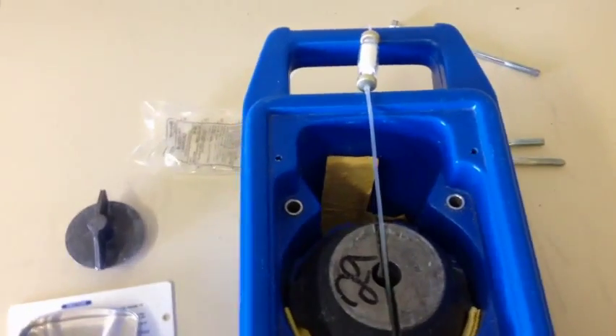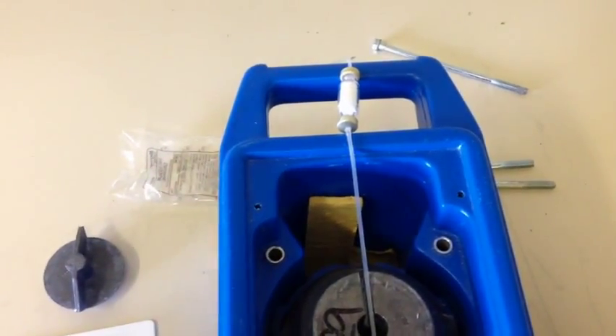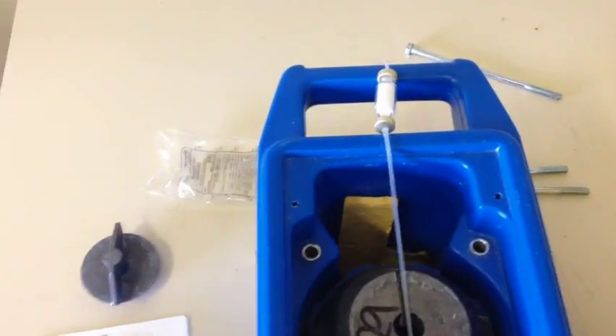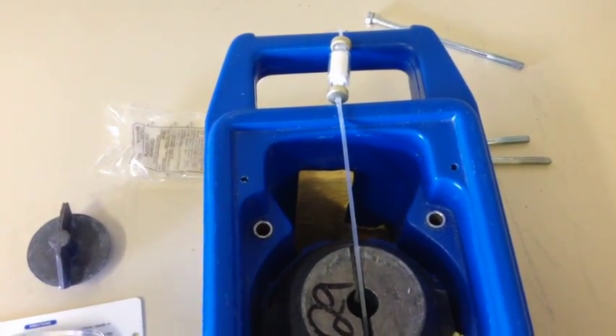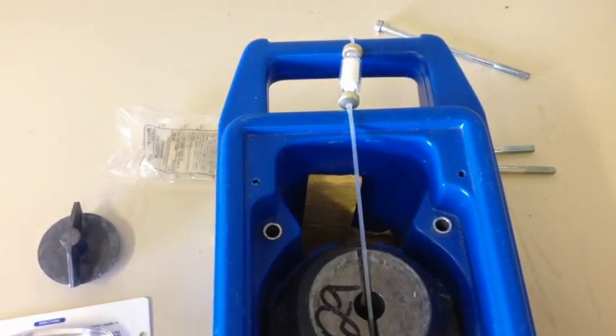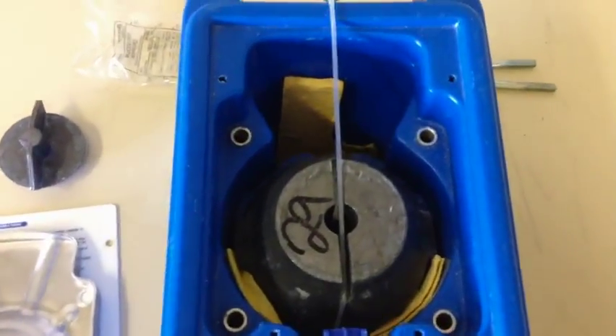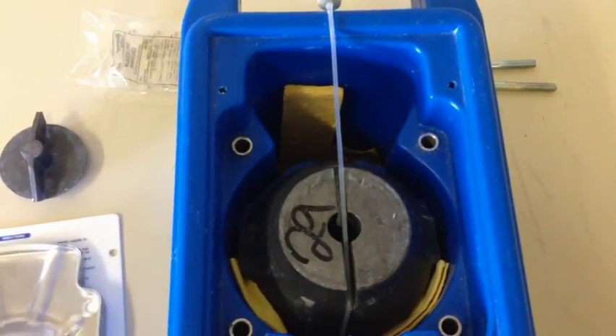You could top it up through the port, but in most clinical environments 250 mils is not going to be eluted in a week. It might become an issue if you're using a generator over a two-week period, with double elutions—a new generator in week one combined with a new and old one in week two. Or more commonly in centralized pharmacies where some of these products might be cycled on two or three elutions per day to generate maximum efficiency in terms of output.